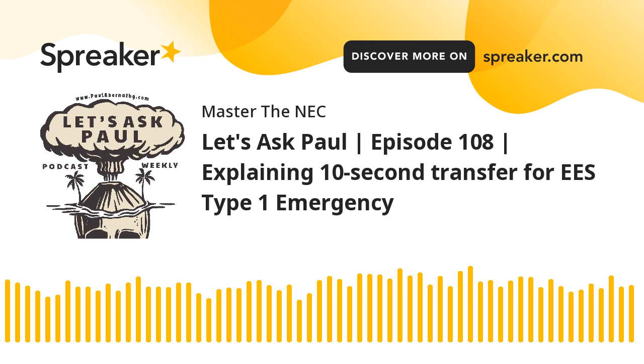I will tell you that a lot of people will challenge you as you become more knowledgeable. I tell people all the time, when you're in our Fast Tracks program and you really start learning the code and coming to our Wednesday night sessions and bringing up these questions, we get into deep thought. Last week we talked about ampacity, and 210.19(A)(1)(a) and (b), and when you apply the 125% for continuous, and when you don't have to, when there's a condition of use involved like an adjustment or correction. Then you get to ignore the continuous load and just treat it at the actual load.